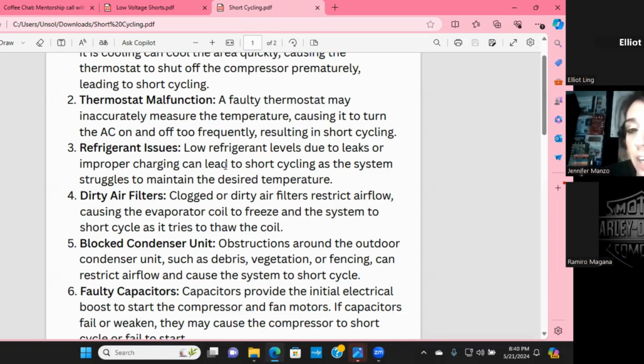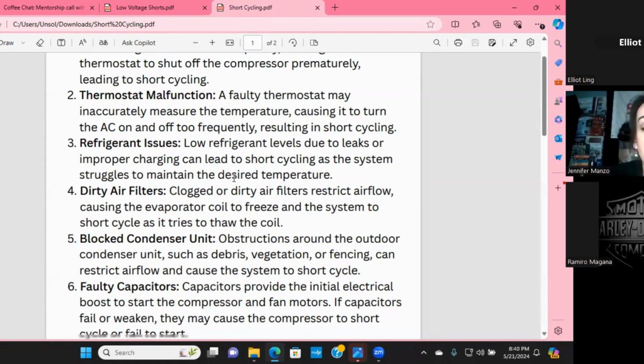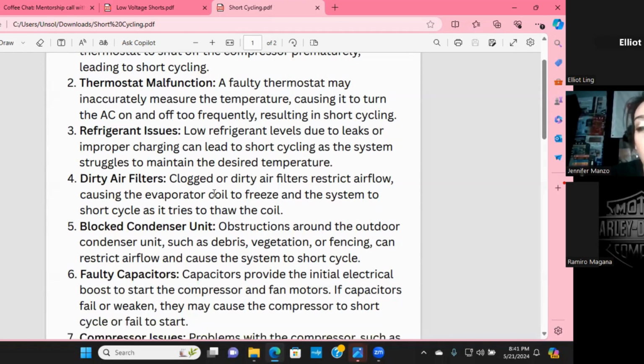Refrigerant issues. This can cause it. It is very prominent. Low refrigerant levels due to leaks or improper charge can lead to short cycling as the system struggles to maintain the desired temperature. So when you have a low refrigerant charge, your compressor is working really, really hard, and sometimes it just can't keep up, and you end up just running for a little bit and then taking a break and running for a little bit and taking a break. This happens a lot. That doesn't necessarily mean that we need to be checking our charge at every maintenance. That just means that we need to be looking for signs that the charge is low.